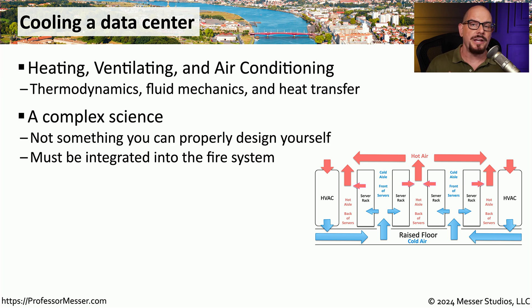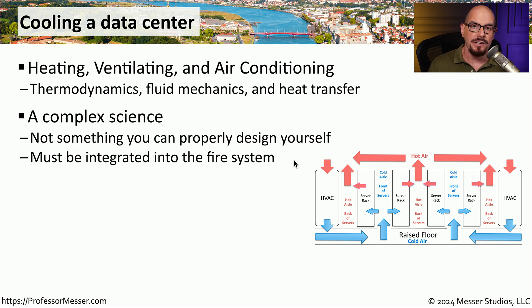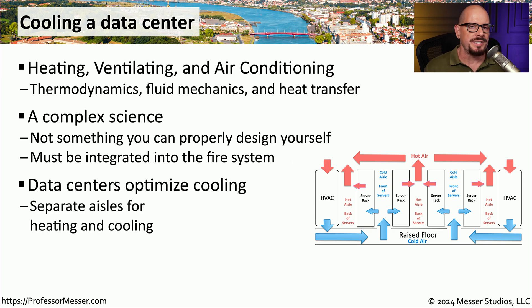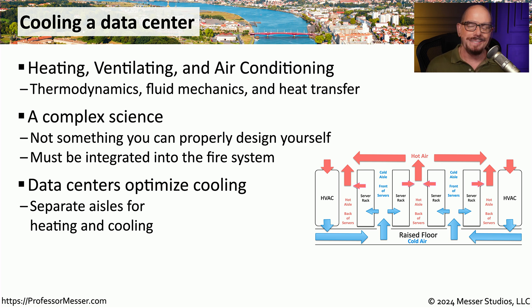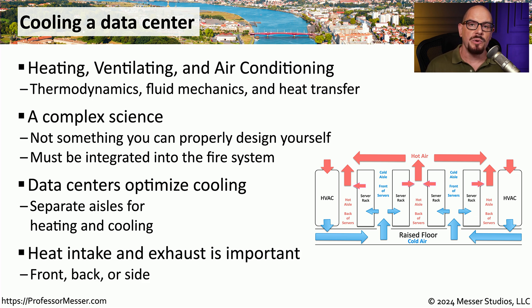We not only need to make sure that the HVAC can support the amount of heat that's going to be created by these systems, we also need to make sure we have enough power to run the HVAC. And we also need to make sure this is integrated into the fire system so that we're able to turn it off automatically if a fire is detected. One thing you'll notice in a data center is that the different aisles may be designated as a hot aisle or a cold aisle, which is an important designation especially as we're installing new equipment. We want to be sure that we're installing equipment in a way where the hot air is being blown into the hot aisle and it's pulling in cold air from the cold aisle.